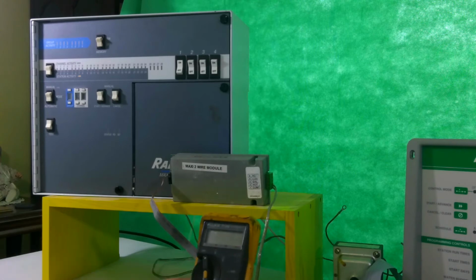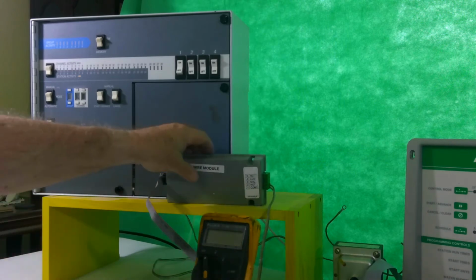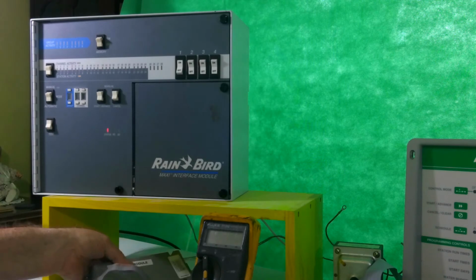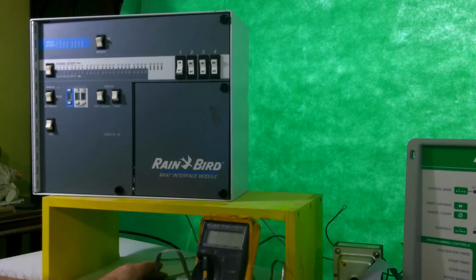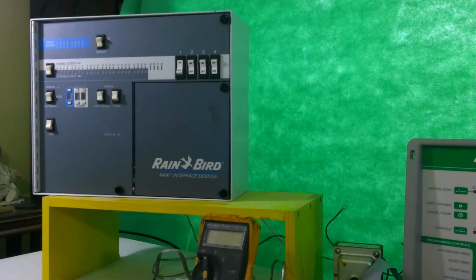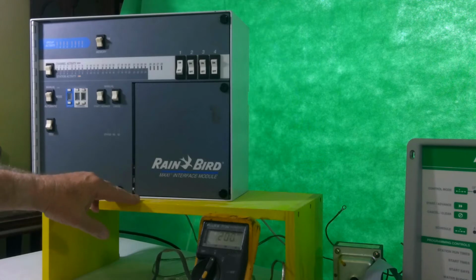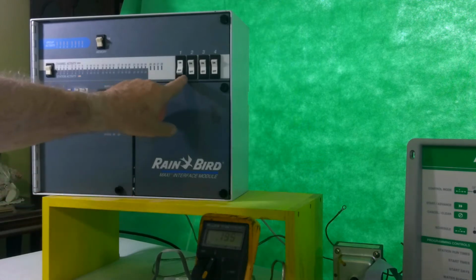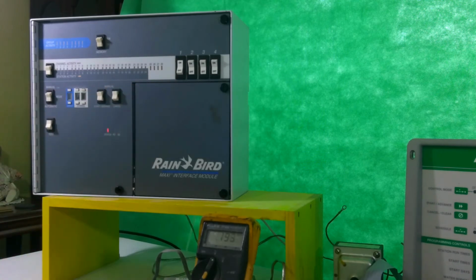So the first thing I'm going to do is move this module out of my way because it's normally out in the satellite. I'm going to set my meter to read AC voltage. That's the V for voltage with a squiggly line. Not the straight line with the dots, that would be DC voltage. I'm going to make sure that the switches for the different channels are on for the ones that I use. In this case it's channel 1, and that is on.